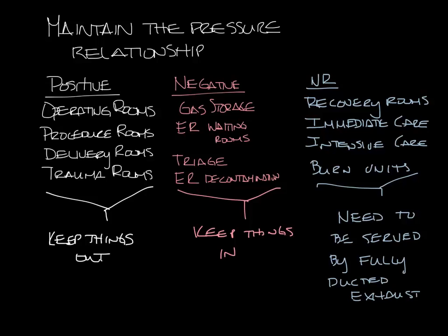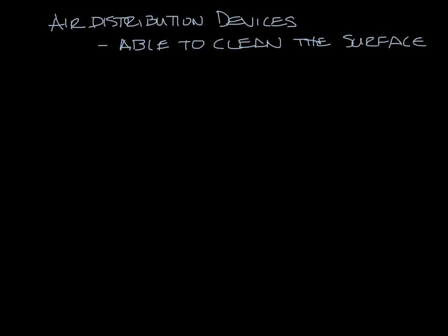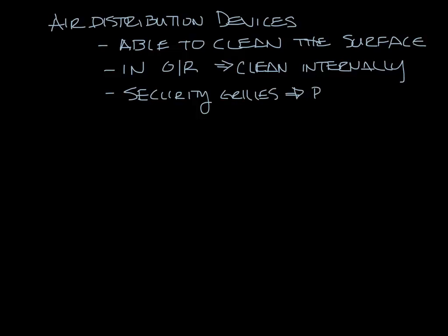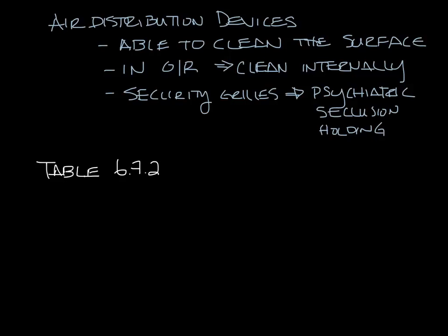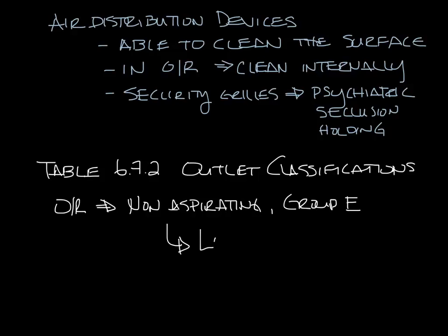Now let's talk about air distribution devices. There are a couple things you need to know about air distribution devices used in healthcare. First, you need to be able to clean the surface of the diffusers, and in operating rooms you need to be able to clean them internally as well. You also have to install security grilles in psychiatric seclusion and holding patient rooms. Table 6.7.2 of ASHRAE 170 tells you what outlet classification to use for the different healthcare spaces. For instance, operating rooms need to have non-aspirating supply diffusers from group E. The groups correspond to outlet classifications in the ASHRAE handbook — these are basically the laminar flow diffusers discussed a couple weeks ago.